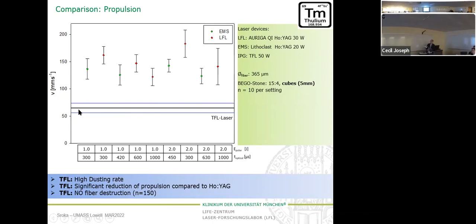So in summary, we can say that this laser-induced shockwave frequency is individually dependent on the lasers used and the choice of the parameters. We can destruct the stones. It is a very efficient way, much more efficient than extracorporeal shockwave lithotripsy. And in principle, it can be done with each laser. But we also need efficiency in the destruction of equipment as well.